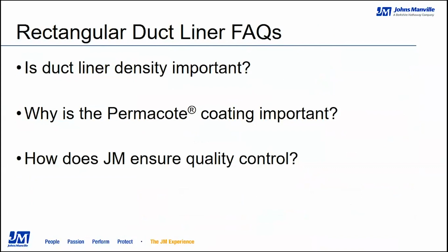The performance-based ASTM C1071 standard basically removed the guesswork for selecting duct system liner insulations and gave the engineer, contractor, or building owner the freedom to focus on comprehensive duct liner performance instead of density and the amount of glass in the product. It meant they could write specifications based on acoustical performance, thermal performance, corrosive potential, surface burning characteristics, and other key characteristics tied to the duct liner. So you might be thinking, well, this ASTM C1071 came around in 1986.